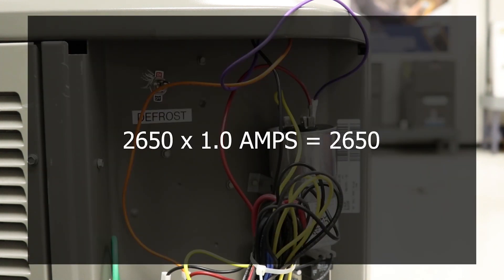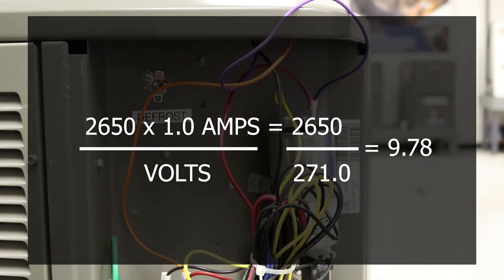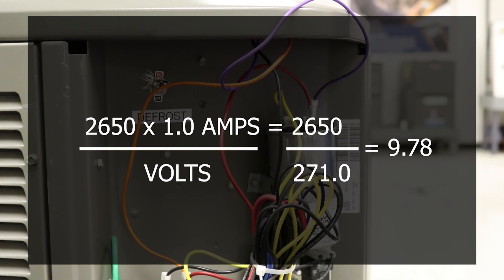So for the fan, we have 2650 times 1.0, which is obviously going to give us 2650 divided by that voltage, which was 271 volts. So that capacitor is running at 9.7 microfarads while it's in operation.